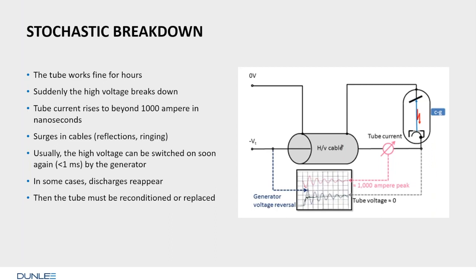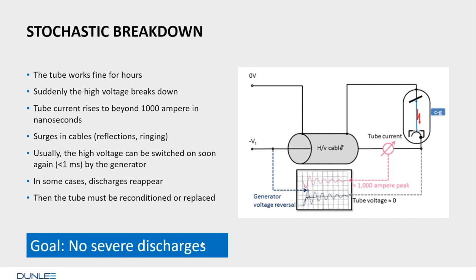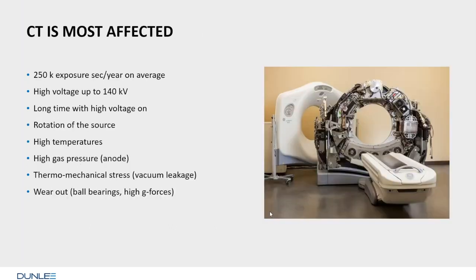Sometimes not. And sometimes discharges may reappear. Then the tube must be handled with some care because it may need a reconditioning, or if something has really been damaged, then it has to be replaced. So what we want is that we have no severe discharges which destroy anything. We will sometimes experience discharges, but we want not to make them too heavy.